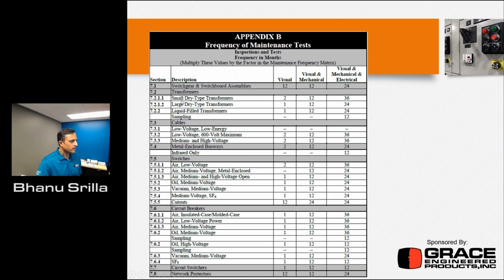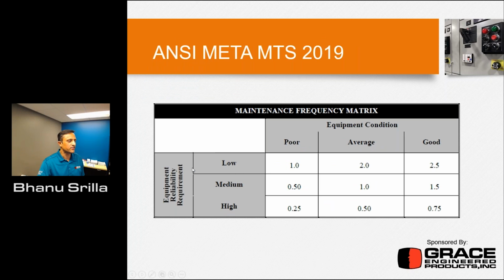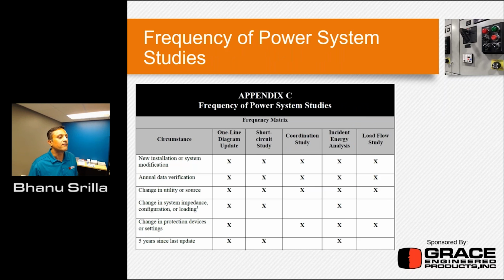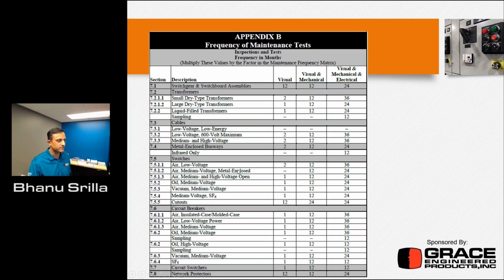So these are the definitive visual and mechanical, electrical, all three different categories of different types of electrical equipment, right? The ANSI NETA standards define this in various buckets, like switchgear, switchboard assemblies, or your low voltage, low energy equipment. For example, let's look at the infrared, visual, electrical, and mechanical, right? It says 12 months here. Then you check this based on your reliability requirements, where you're looking at the reliability needs, and evaluate the condition of the equipment as it says, and you apply that factor, and that's the frequency you should be using when you're performing this type of test. Okay, this is a good reference chart.